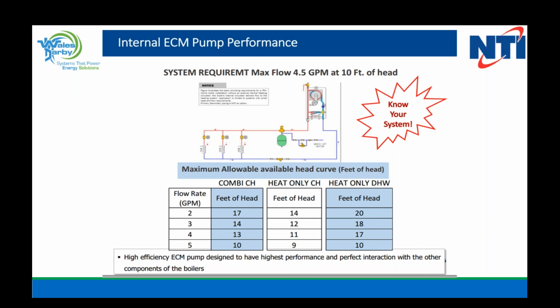So really the lowest flow rate would be 2 GPM. Again, at a 20-degree delta, that's 20,000 BTU. So if we're at that lower flow rate, we have the possibility of overcoming a little higher pressure drop. And as the flow rate increases, that feet of head comes down. So we show you the column for a Combi system. And when you see CH, that means central heat, heat only. So that's just making heat, no domestic hot water, or heat only with domestic. You can see the column there for the amount of head that we can overcome based on GPM.